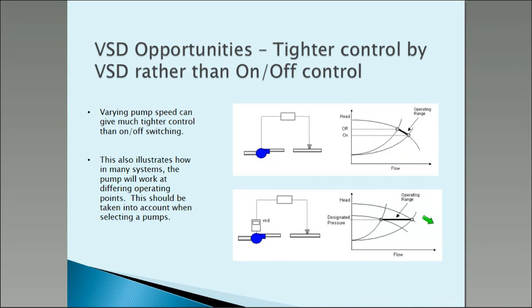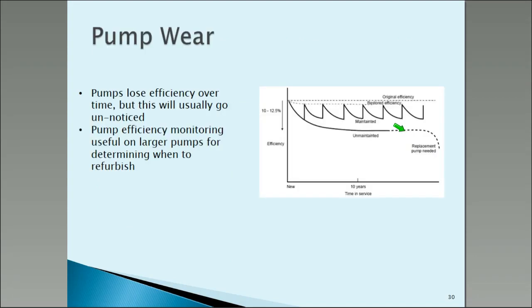A variable speed drive doesn't just save energy — it can also give you much tighter pressure control. You can have a variable speed drive driving a pump continuously backwards and forwards, rather than just occasionally turning a pump on and off. One interesting point is that in a real pumping system, there's not just one operating point — the pump will be working over several different operating points. That has implications for your choice of pump.